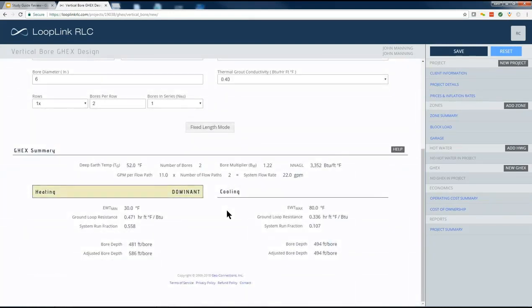Just to show you a couple things to be aware of here. Now that we've done that, the first thing that you always want to look at is how many GPM you're pushing through each loop, or the GPM per flow path. You can see 11 GPM through a 1.25 inch loop. Especially down here, you can see they're coming out to almost 600 feet. You'll definitely want to check your numbers here and make sure that at that flow rate, your head loss isn't becoming excessive and pumping power isn't going to become a concern. So 11 GPM might be on the high side. Might consider going to 3 loops instead of the 2 for this example here in the 7 tons. So we're going to get closer to about 2.5 GPM or tons per loop.